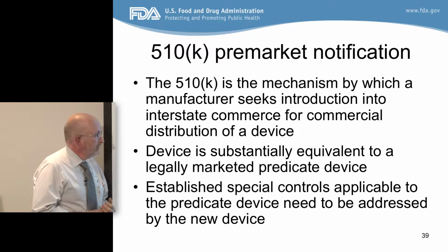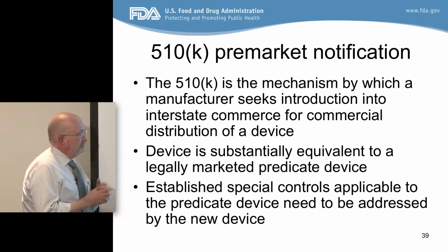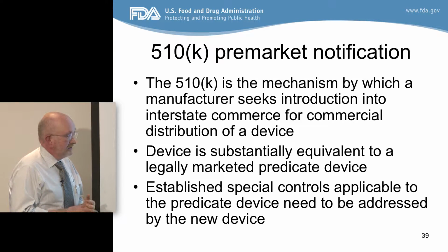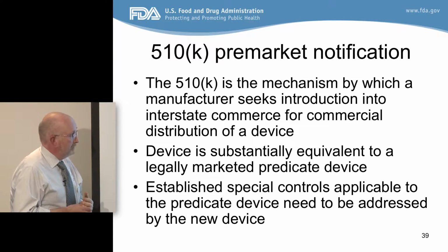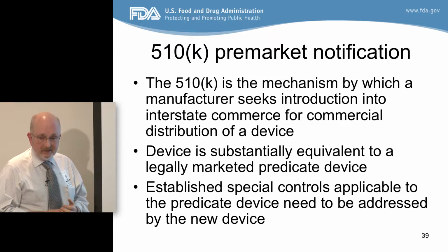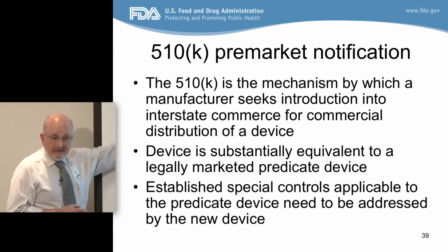So the 510K process, that class 2 process that I was talking about, is the mechanism a manufacturer uses to see how FDA is going to regulate their device.